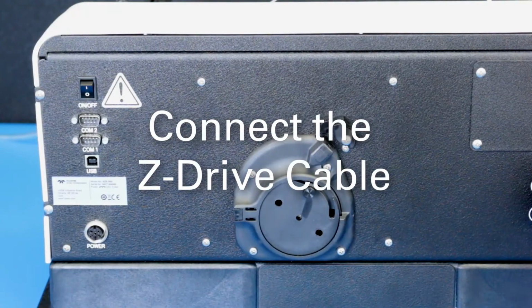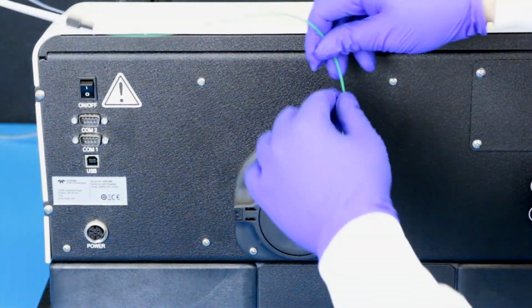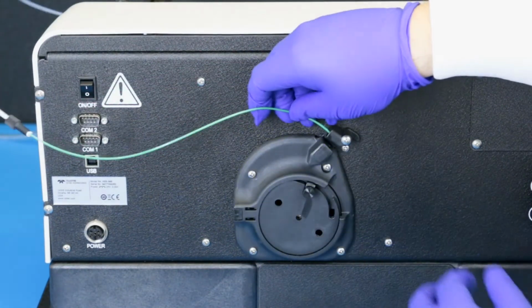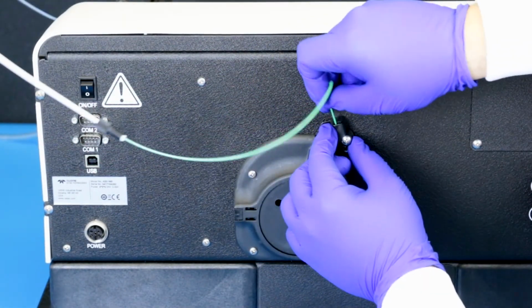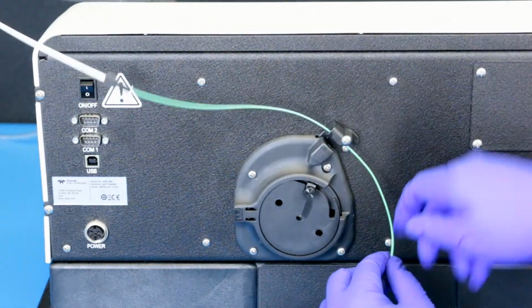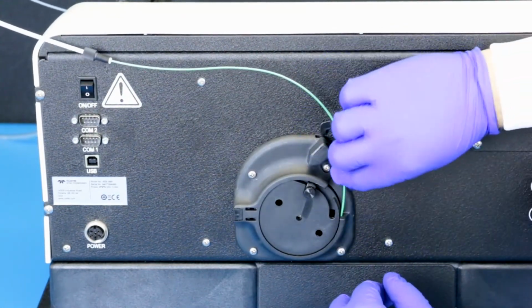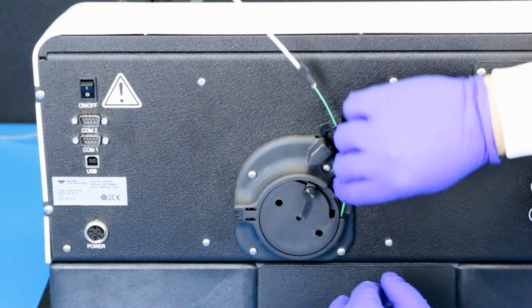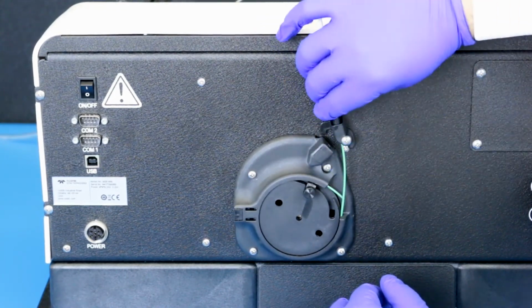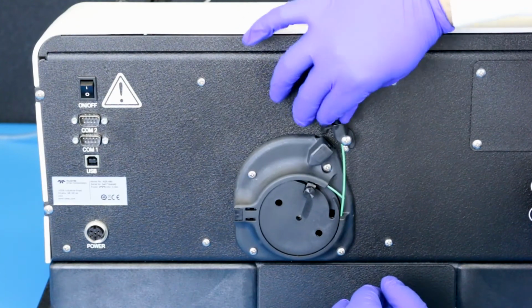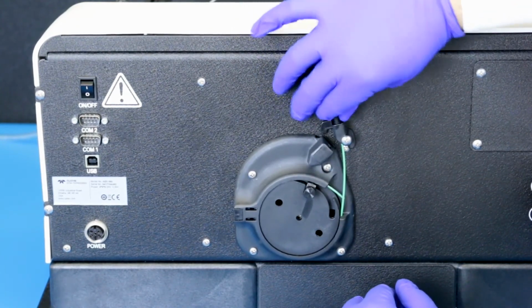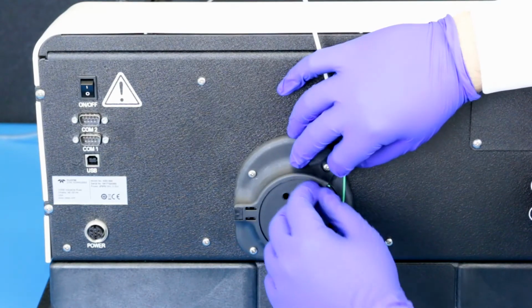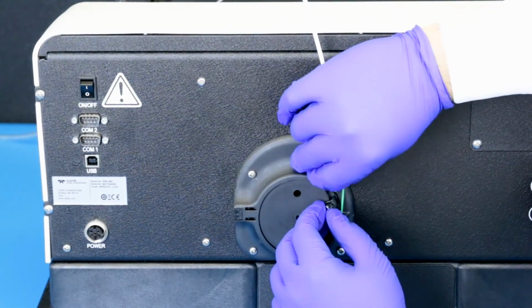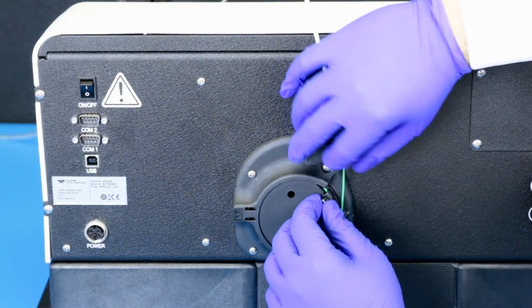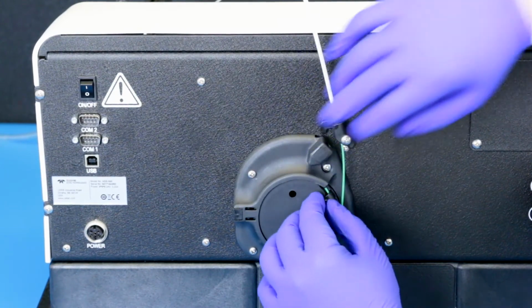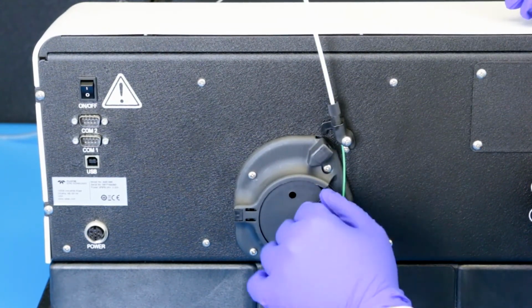Connect the Z drive cable. Feed the cable through the rear guide block and around the rotor. Tighten the nut to secure the cable sleeve to the guide block. Position the cable so about 2 millimeters of cable extends past the clamp. Hold the cable against the rotor and secure by finger tightening the thumb screw.